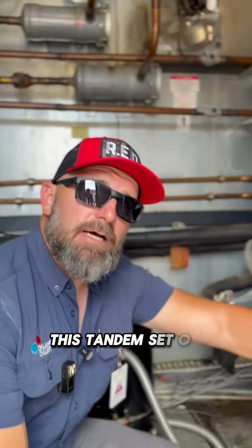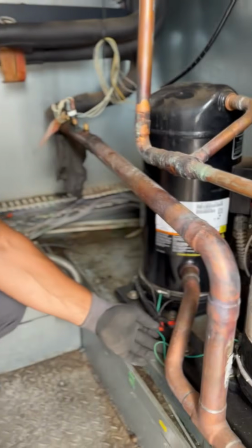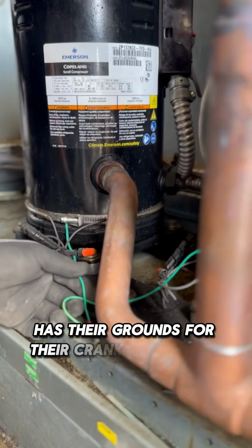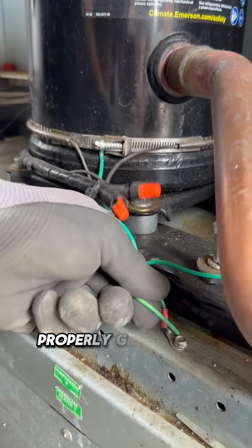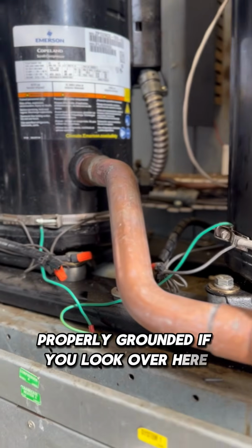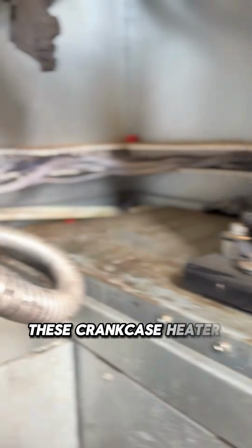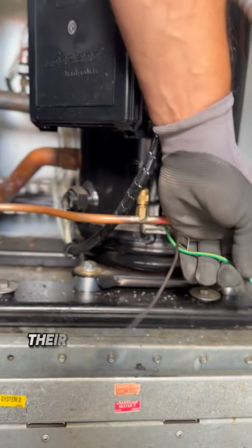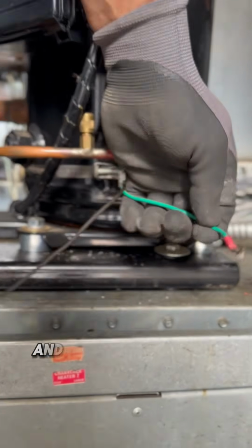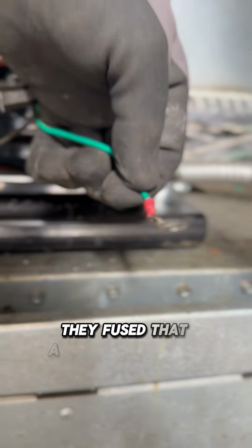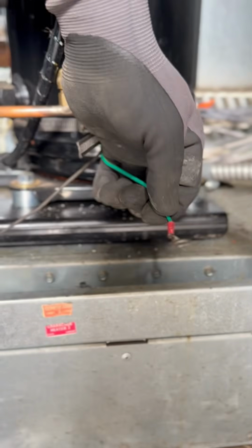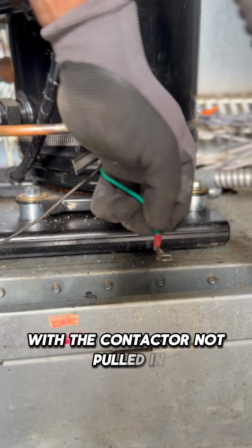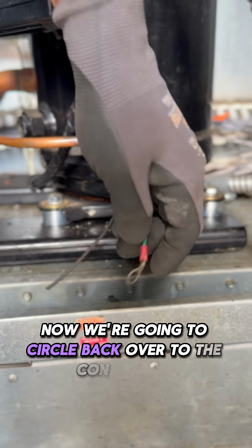This tandem set of compressors has their grounds for their crankcase heater strips properly grounded. If you look over here, these crankcase heater strips have failed in the past. Their grounds were not properly connected, and what they did was they fused that auxiliary contact together with the contactor not pulled in. Now we're going to circle back over to the contactors.